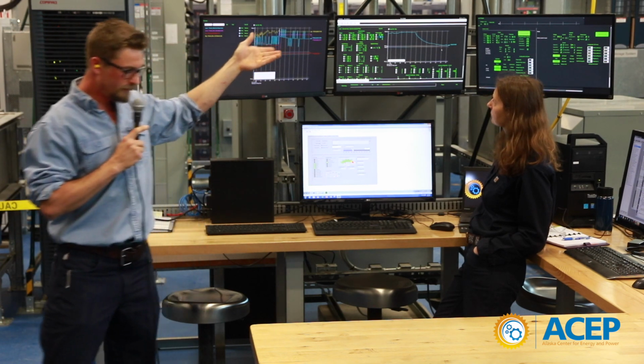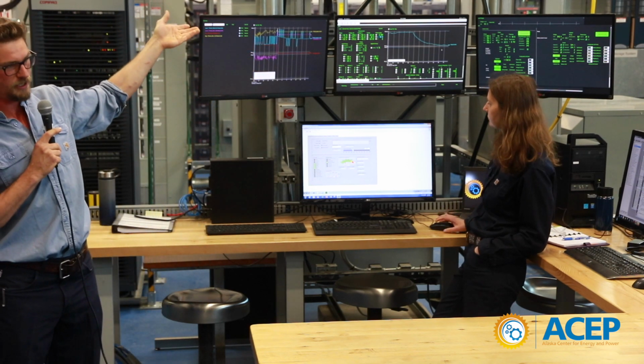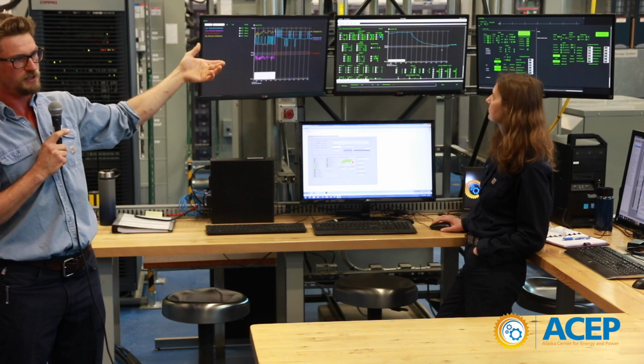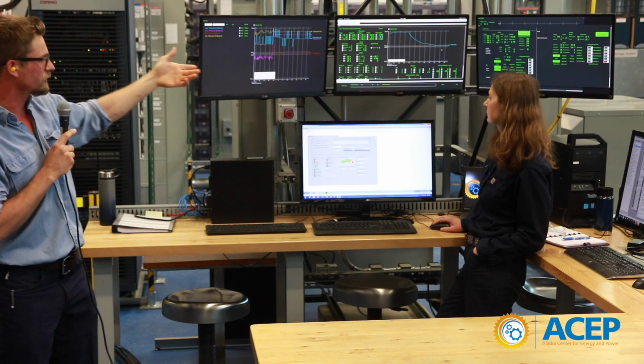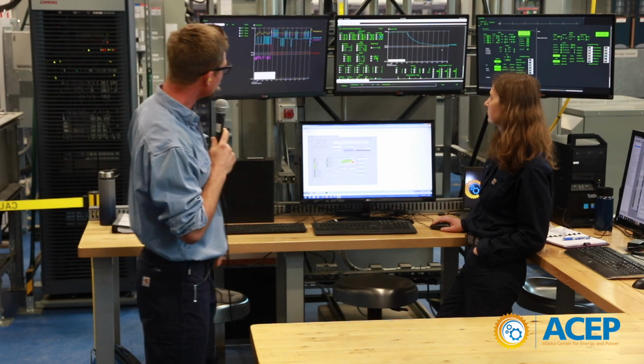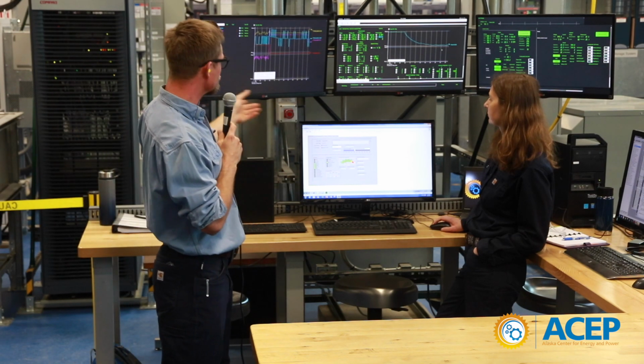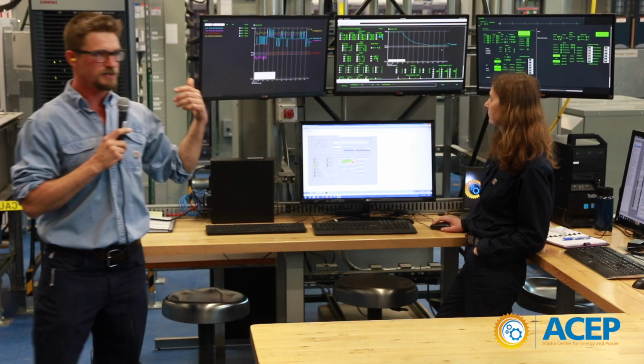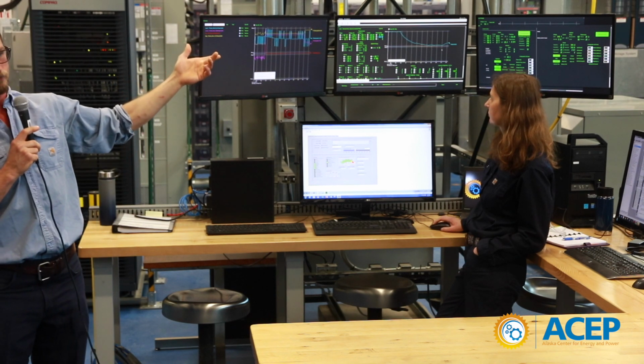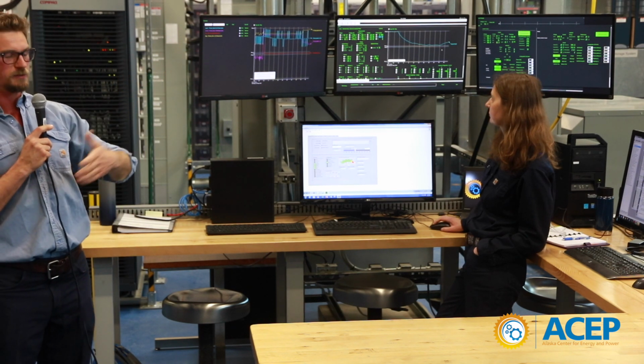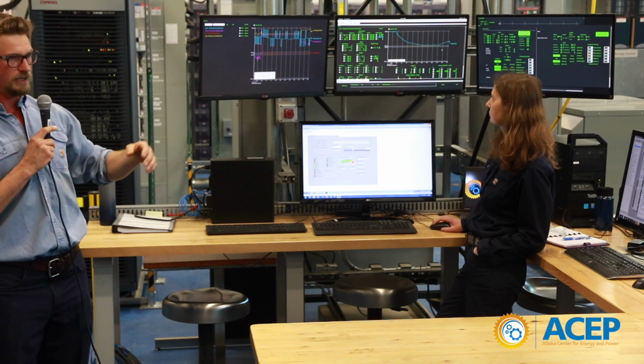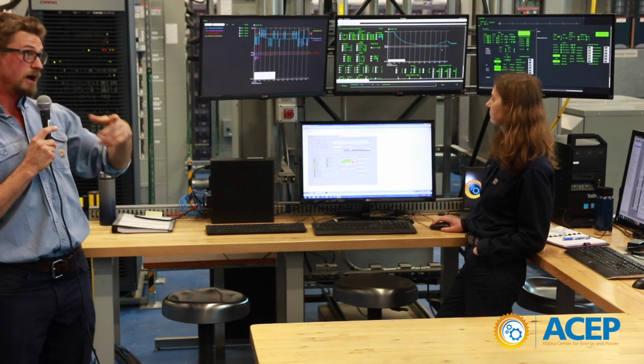Basically, this inverter is providing the same services that the diesel generator was providing — it's forming the grid. Now if our wind power goes up and down, the inverter does the same thing the generator was doing: it balances out the difference between the wind power and the load.